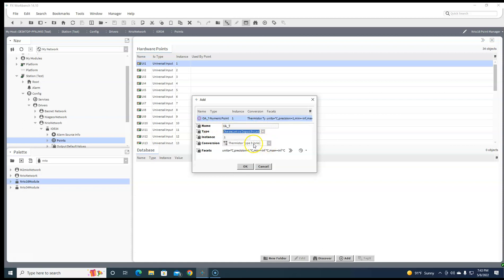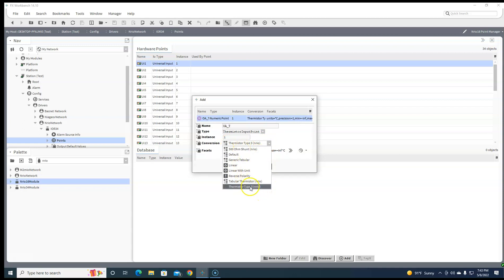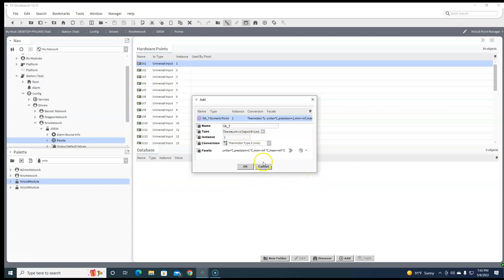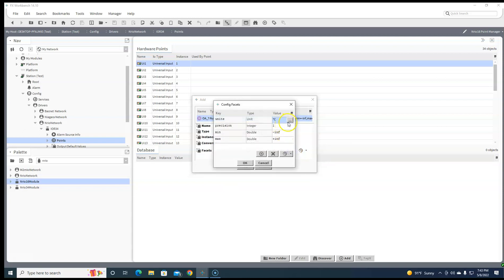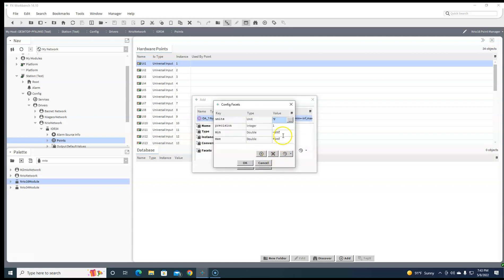So 10K type 3 is the only one that you can choose in the drop down. Everything else you're gonna have to build a curve for, so it's just best to get it into 10K type 3 sensor. Where I'm from, we use Fahrenheit, and since it's outdoor, we'll give it a negative 50 to a 150.